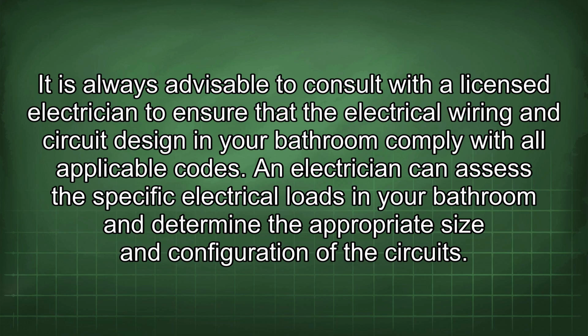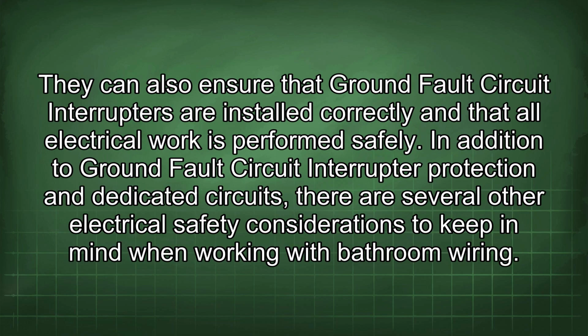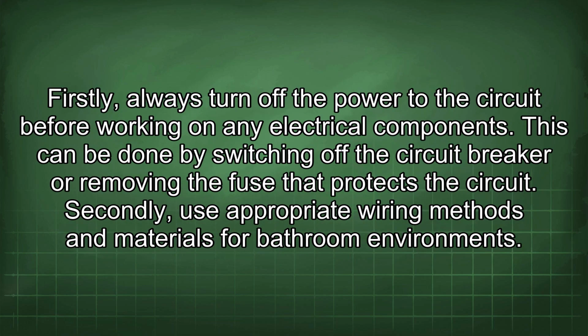An electrician can assess the specific electrical loads in your bathroom and determine the appropriate size and configuration of the circuits. They can also ensure that ground fault circuit interrupters are installed correctly and that all electrical work is performed safely. In addition to ground fault circuit interrupter protection and dedicated circuits, there are several other electrical safety considerations to keep in mind when working with bathroom wiring. Firstly, always turn off the power to the circuit before working on any electrical components. This can be done by switching off the circuit breaker or removing the fuse that protects the circuit.